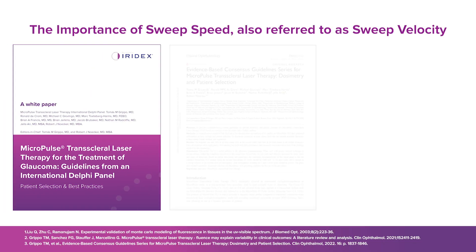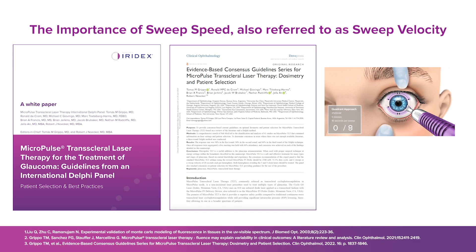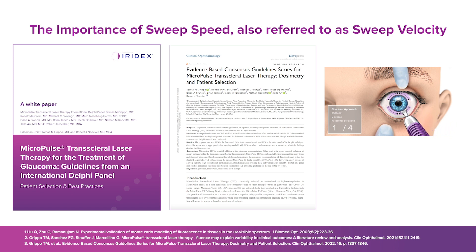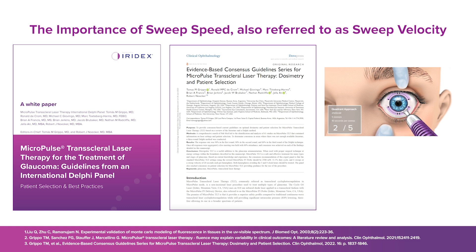Based on the science of advanced tissue modeling, peer-reviewed literature, and findings from the Micropulse TLT international consensus, steady sweep velocity is an important treatment variable to achieve safe and effective clinical outcomes. The slower the Micropulse P3 probe is swept during treatment, the longer the laser energy dwells and is absorbed in the underlying tissue.